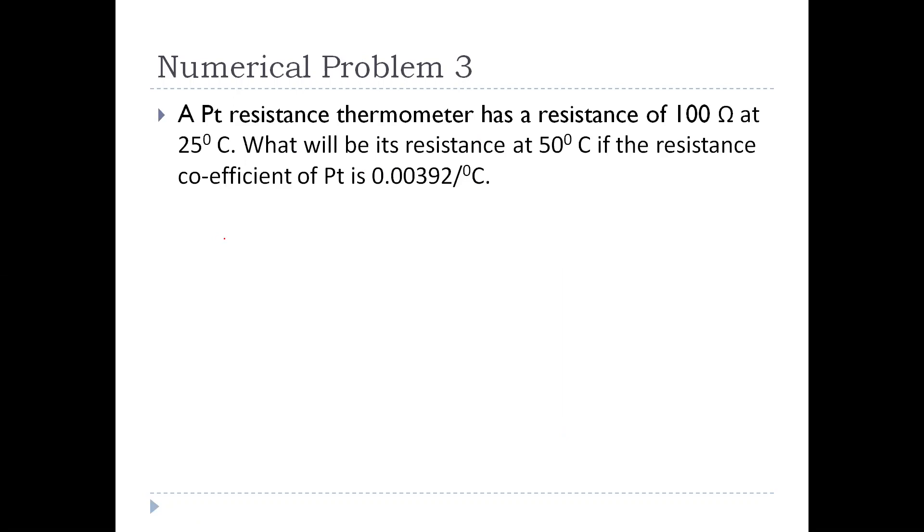For RTD, we have only one formula: RT is equal to R0 into 1 plus alpha into delta T. R0 is the known resistance, RT is the unknown resistance, alpha is the resistance coefficient and delta T is the change in temperature. Here the known resistance is 100 ohms at 25 degree Celsius. We have to find R50, the resistance at 50 degree Celsius. Delta T is 50 degree Celsius minus 25 degree Celsius, which equals 25.